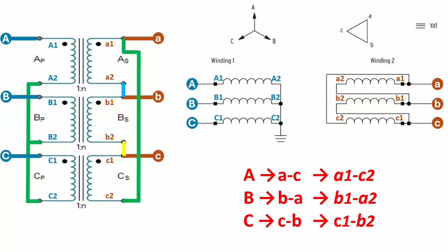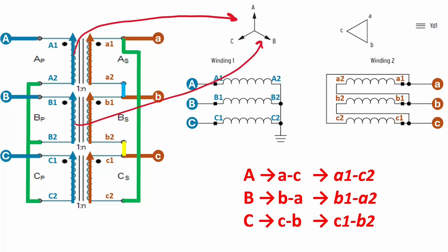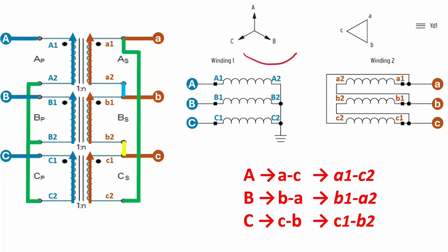And then the next thing that we're going to talk about is all we're going to add is arrows for our vector diagram. Okay, and all that means is if this is the A phase arrow, it's right there. B phase arrow for primary and C phase arrow is right there. And so we're just creating arrows. Okay, and we know what the phase rotation is. We know that these phasors are rotating in that direction. It comes A phase first, then B phase and C phase. So we already know what the angles of these arrows should be anyways.